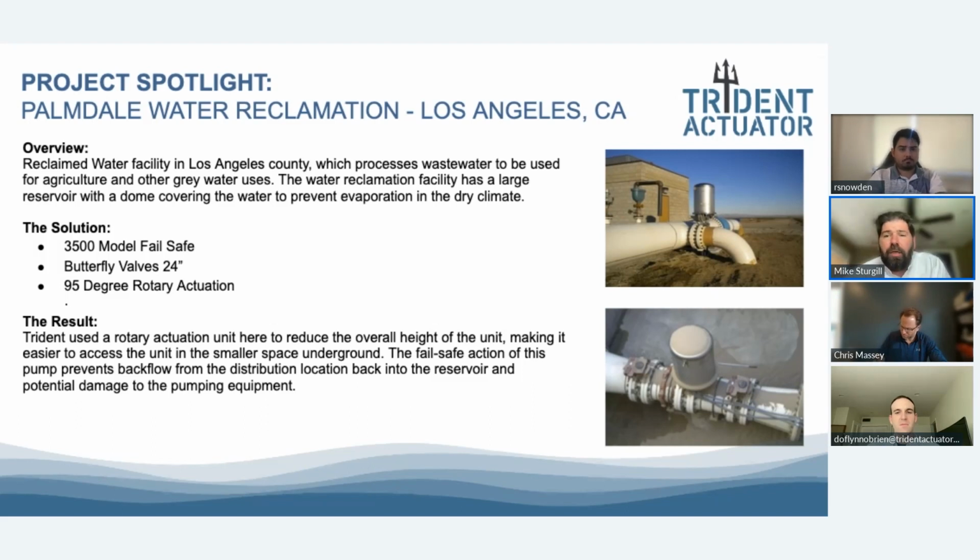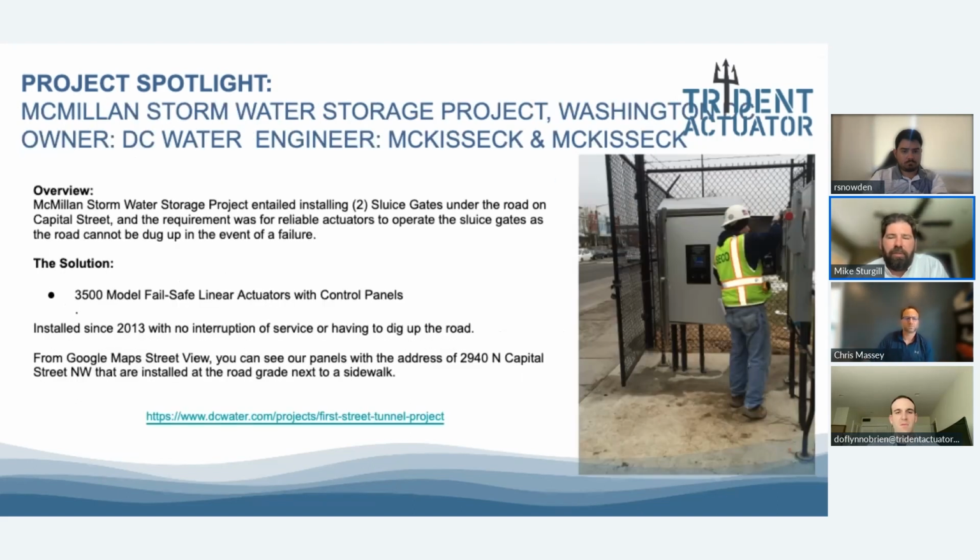actuators. They're underground out in Washington, D.C. They had 2 sluice gates that they wanted installed, and they wanted reliability, since they can't dig the road up. So we've been underground for over 10 years with no interruption in service on both of those. You would only know they're there if you were walking at grade and knew what our panel looked like. So you talk about reliability, you haven't had to mess with that in 10 years and dig up the road. So really a staple for us.